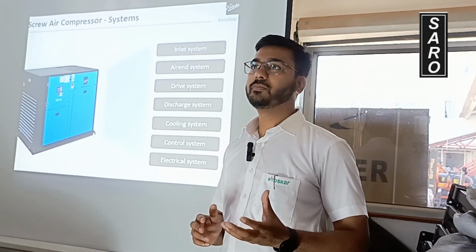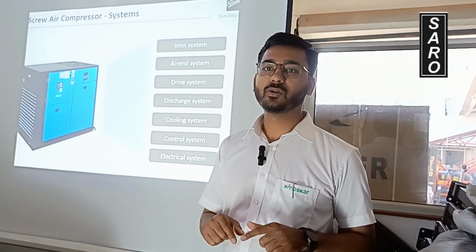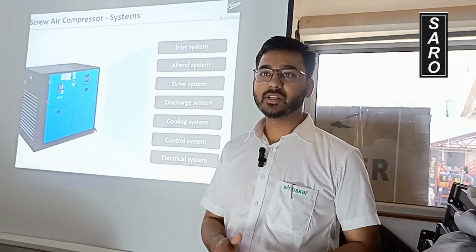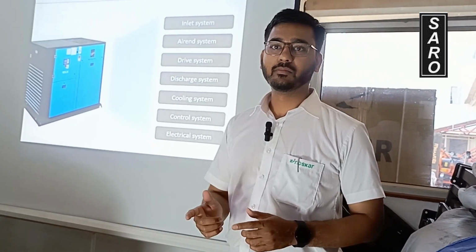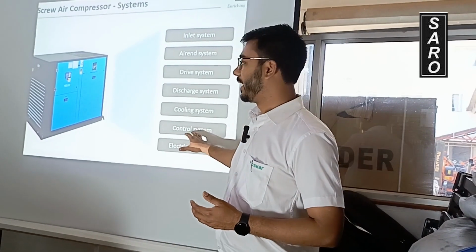If the oil temperature goes beyond 120 degrees, then we have the setting in the controller that the compressor should trip. If it is 110 degrees, there should be an alarm in the system. So there are programs in the controller, and according to that, the control system acts.